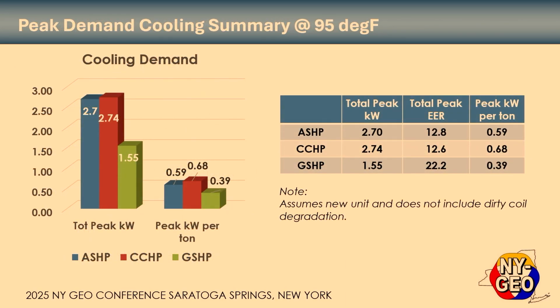Okay. So here we have on the cooling demand side, the actual peak demand in kW. You can see that the air source and the cold climate heat pump are very close for the cooling demand. And you would probably expect that at 95 degrees, the vapor injection isn't necessarily needed, so the two are going to act pretty similar. But keep in mind, if you don't size for heating, this number could actually be smaller, right? Because the equipment would probably be a ton less in most cases, if not even more than that. And so it's very difficult to look at cooling demand without knowing how you've sized the equipment. That's why we went through that whole exercise.